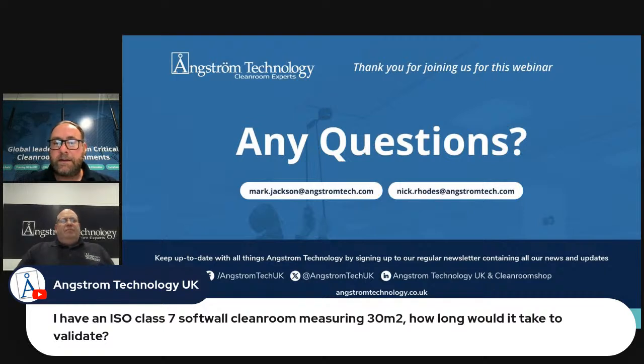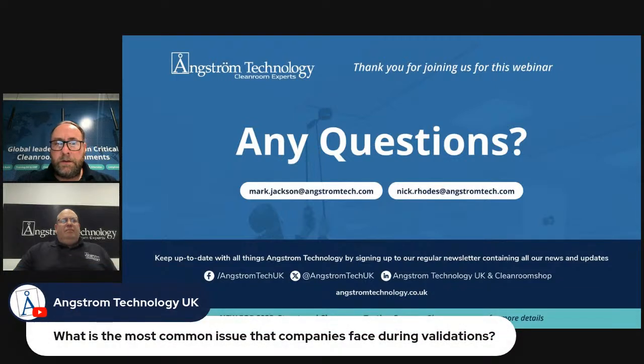Another question that we've been asked. So I think it's come up on the screen. What are the most common issues that companies face during validations? Obviously, the most common one is quite simply that it's failed on particle counts. As we covered earlier in this webinar, this could be down to maintenance issues or lack of training of employees. The engineer on site should indicate to the customer whether this is a mechanical failure, such as maybe fans or HEPA filters failing. But they may also indicate if it's down to user practice, and that potentially these are adding to the types of failure. We would say pre-planned maintenance and user training can and will reduce all these issues. So hopefully that answers that question.